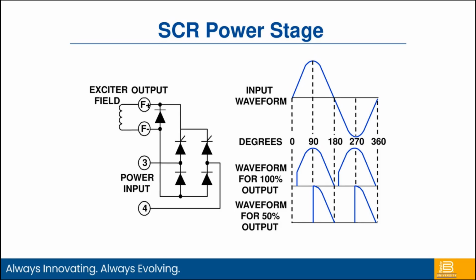In this case, at 100% output, you can see at this first line that I'm taking both the positive side of the sinusoidal waveform as well as the negative side and fully gating it on. If I only need 50% of the output, I'm going to delay the gate of that SCR and only allow half of the AC waveform to go through. So that's an SCR based power stage.